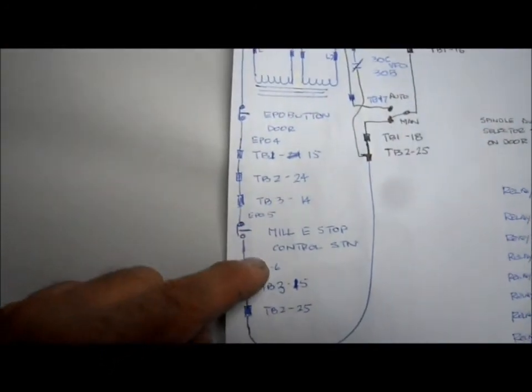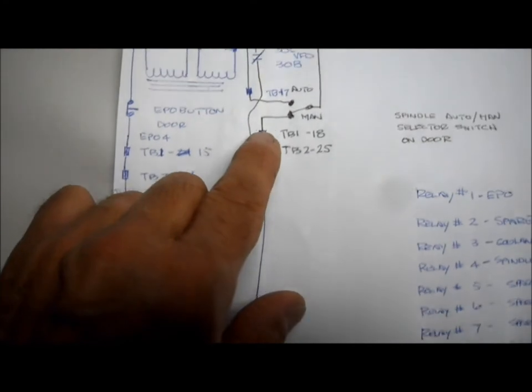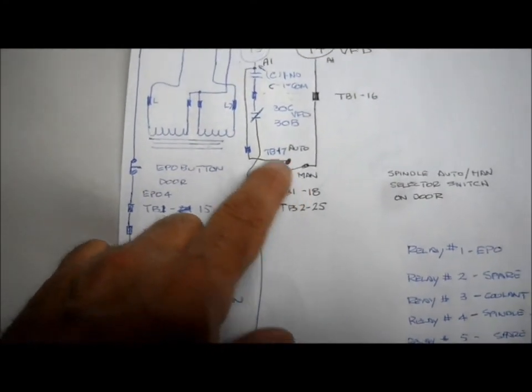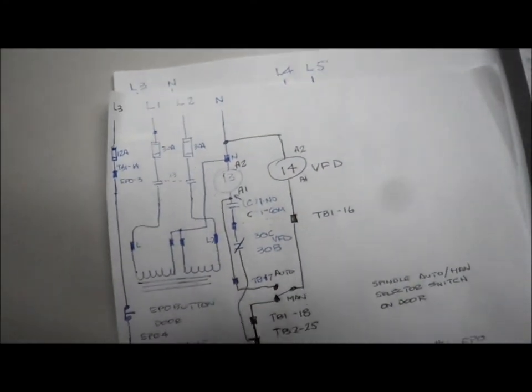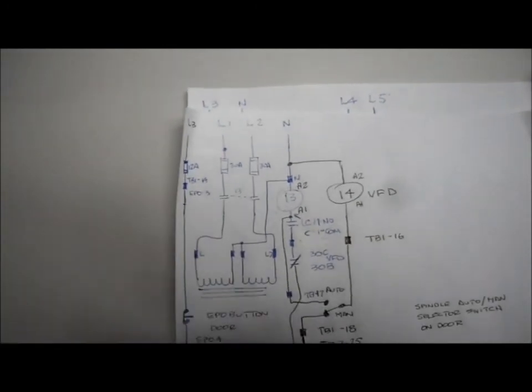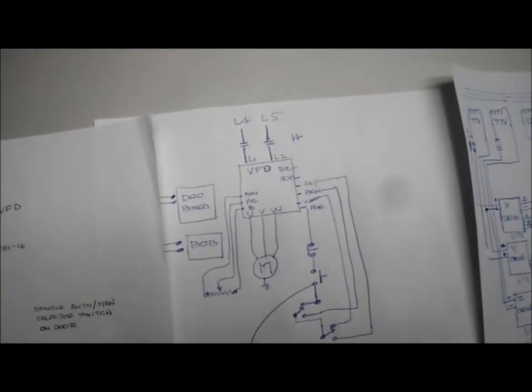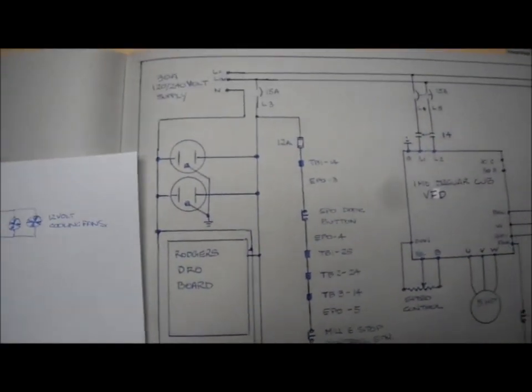Then jumps from TB1 to terminal block two to terminal 24 and keeps working its way all the way down, as you can see, until it comes back into the hand selector switches and the relays and the contactors. That rough idea, you kind of get it on paper and an idea what to do, and then you bring it over.